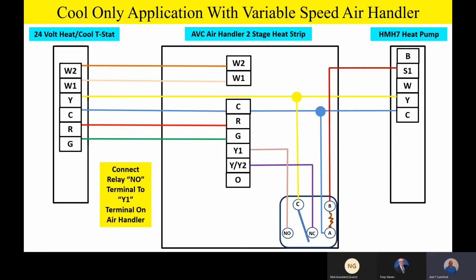But please remember, one more time, even on straight cooling, please put that bi-flow filter dryer on that liquid line, because if you get in a situation where the unit is exercising that reversing valve or going into the heating mode just real quick to return oil and all that kind of stuff, we want to make sure and have that bi-flow filter dryer on there by all means.